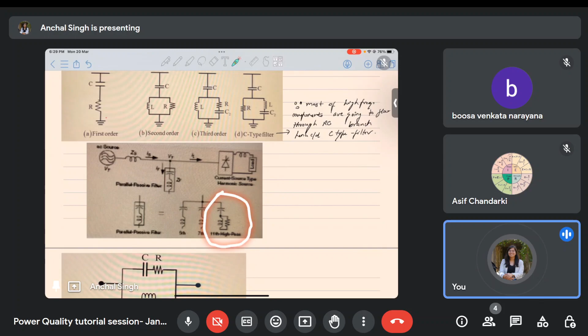If I have fifth and seventh harmonic and other higher order harmonics to take care of, I'll have one branch for compensating the fifth harmonic, another branch for the seventh harmonic, and one more branch for the rest of the higher order harmonics.